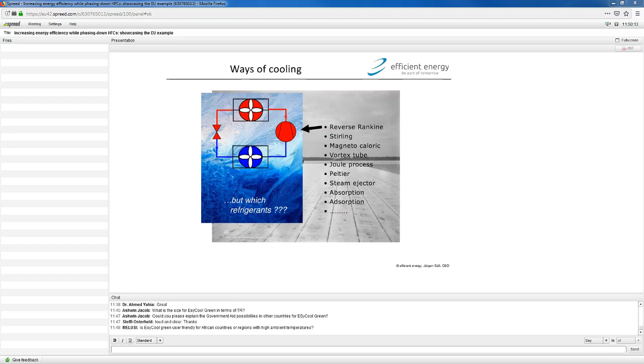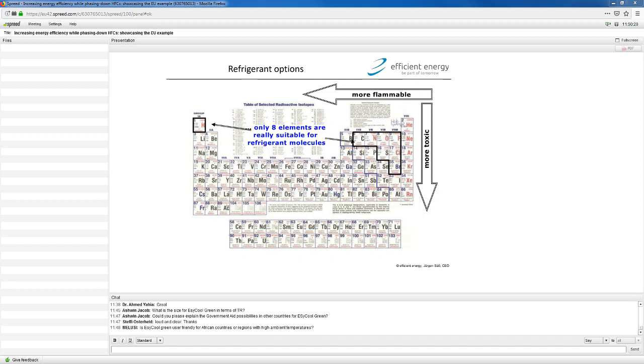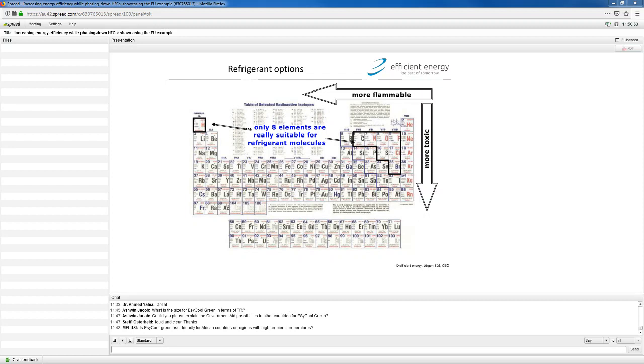There is this periodic table of elements which hasn't changed over the last years, and I think it will not change in future. I mean, some people are afraid of this table, but on the other hand, you can say that we have this toolbox—only eight elements are suitable to be used to build molecules which behave as refrigerant. Nobody should get confused when the chemical industry says they have new refrigerant options and there are coming new solutions. They cannot use anything else which is not available from this table of elements, and the thing is the more you go to the left, like C and H hydrocarbons, the more flammable it gets.